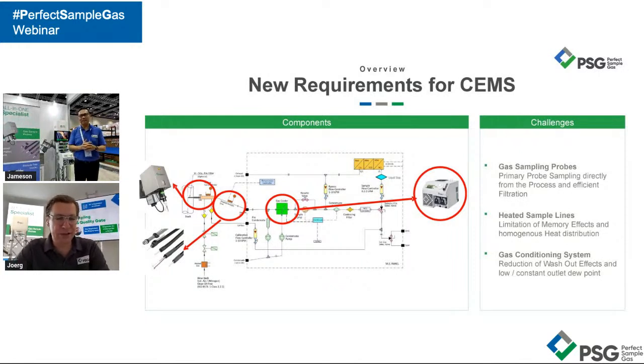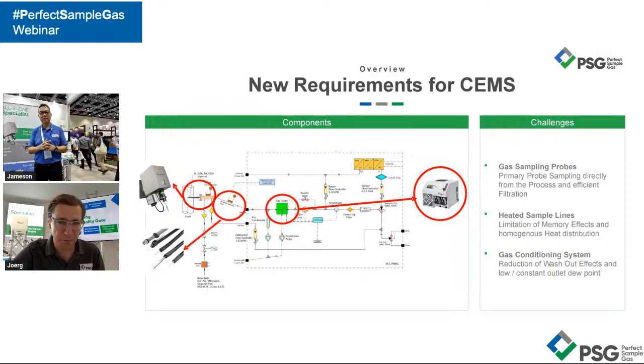Yeah. Okay. So what Jameson just said is a very important fact, which is that the gas sampling probe, sometimes also called the primary sampling point, is exposed to the process. So this probe is handling all the, let's say, very high demanding conditions in the process. And we always say, if there's any problem you can solve in the probe sampling, at the primary sampling point, do it. Just make sure you remove all of these. For example, if you have to handle dust, even if there is a chance to remove it in the first stage.